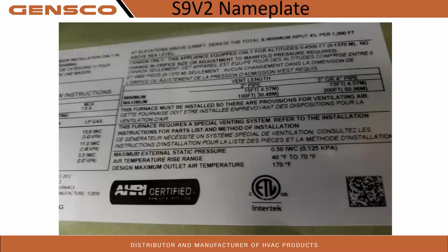Here's a good snippet of an S9V2. And you're going to see that maximum external design static pressure is 0.5 inches of water column. Air temperature rise range: when we're diagnosing heat exchanger and E04 limit switch trips, lockouts, we look at that, air temperature rise 40 to 70 degrees. So if we've got a 70-degree return air, our max we should be putting out is 70 plus 70, which is 140. If we start getting over that 140-degree mark, why? We could have some restricted airflow causing that heat exchanger to overheat, and we're limiting out right around 160. Maximum outlet temperature is 170. That's what it's tested at, but our limit switch cuts out earlier than that. So between 140 and 160, our limit switches will be set.